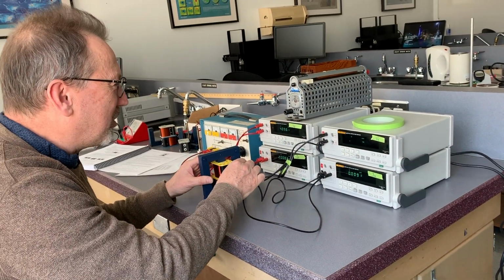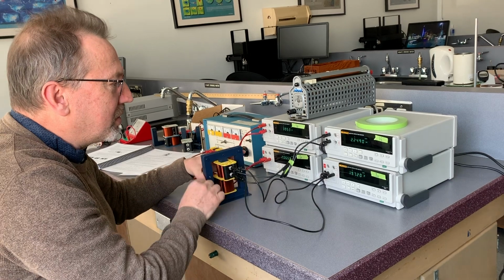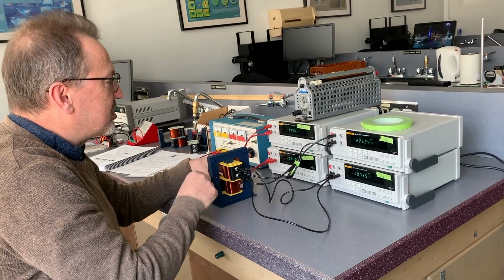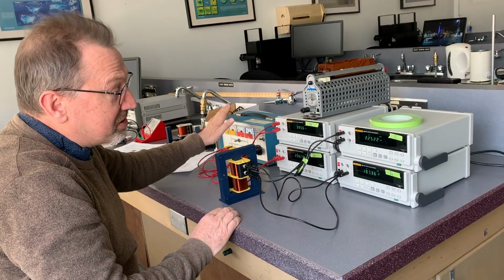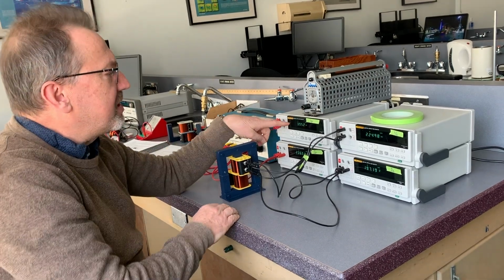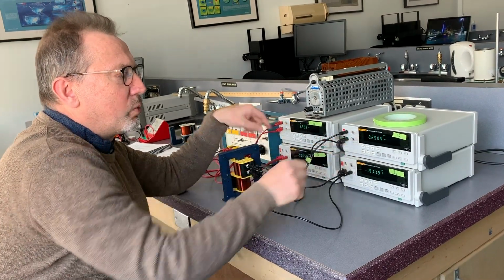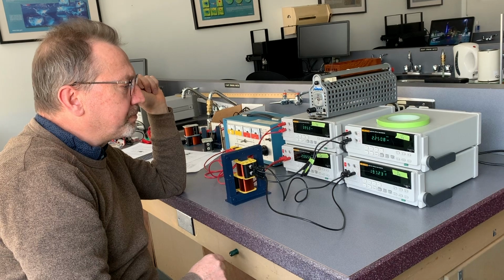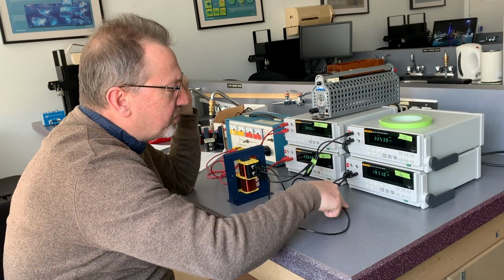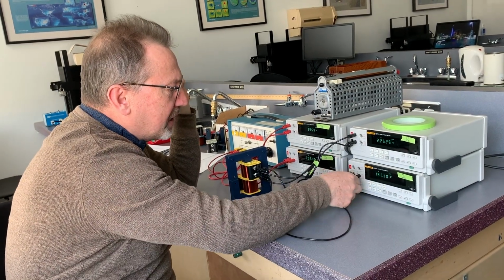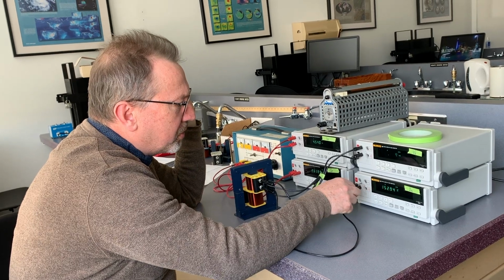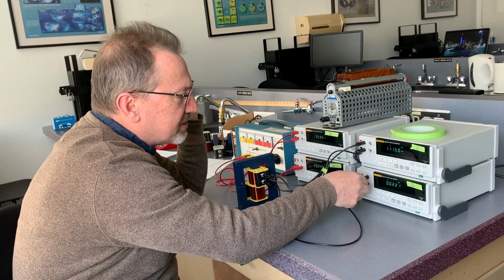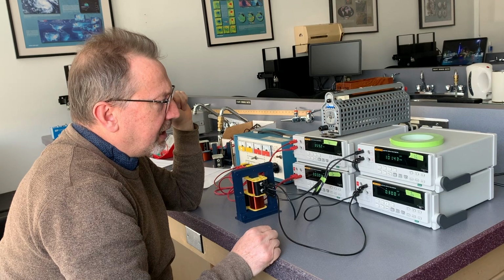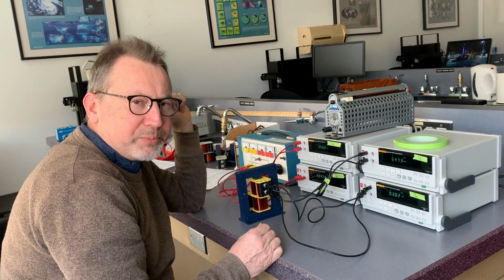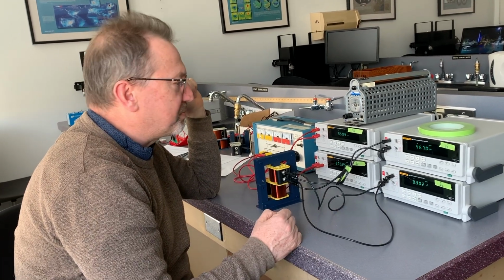But when I put a big nasty load on the secondary, the voltage on the primary collapses again because of the supply. It's not behaving like a one-to-one transformer anymore. That's one data point, then we'll put 10 amps here, a lower resistance, for the last data point with the least resistance possible.